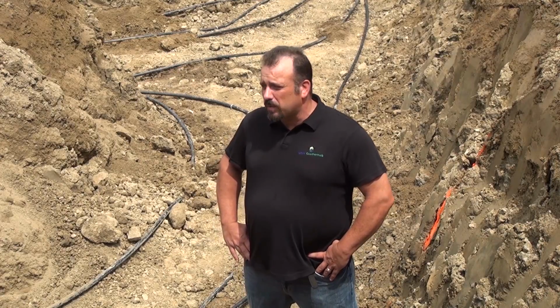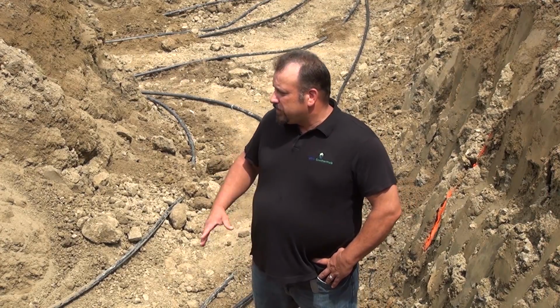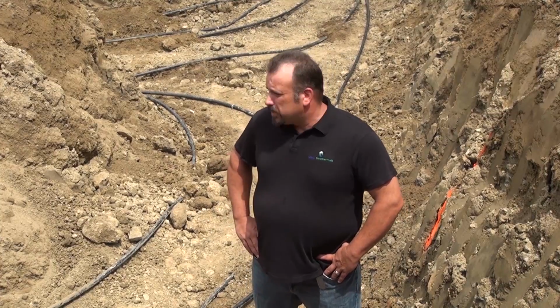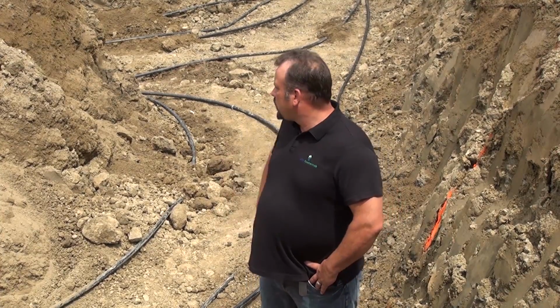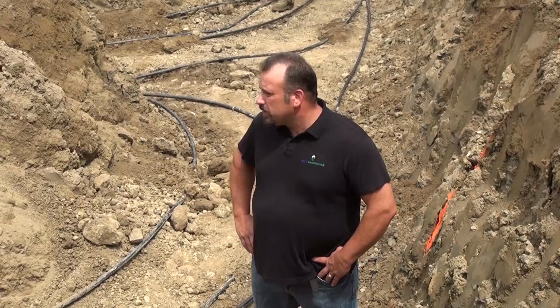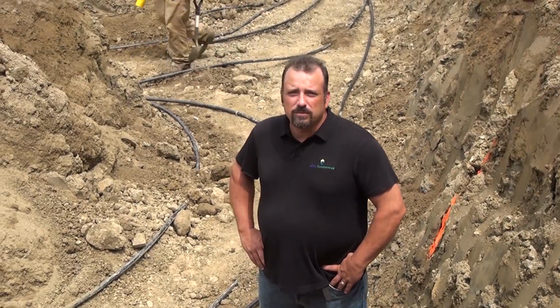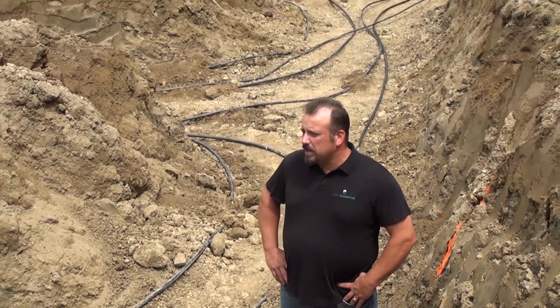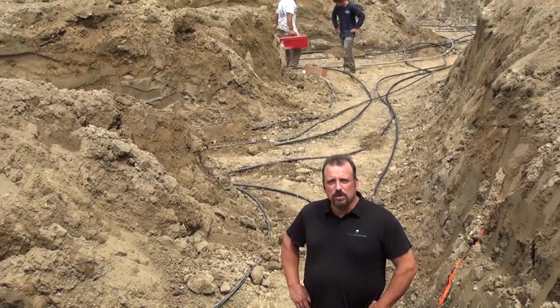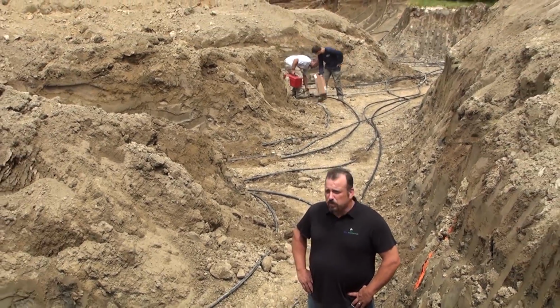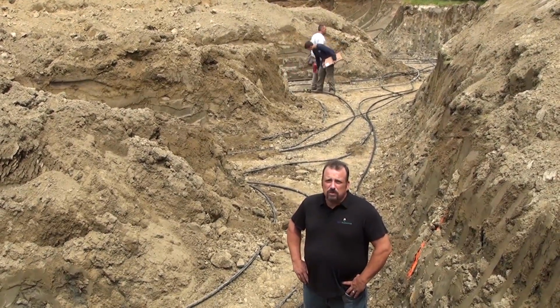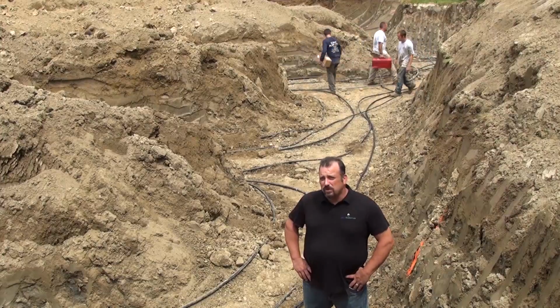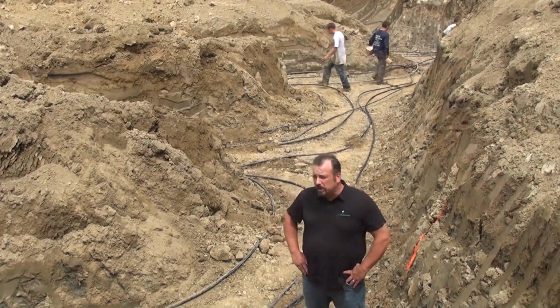What actually heats and cools your home, and the efficiency factor in your heat pump machine or in geothermal, is the refrigerant itself. So this is designed at about a 32 degree loop for the winter time. When a 32 degree loop goes into the home, it'll actually add about 3 degrees of temperature to the refrigerant as it becomes a hot gas, and then will go to your heat pump's evaporator and create heat of about 90 to about 95 degrees Fahrenheit, which is very comfortable and can heat a house very comfortably.